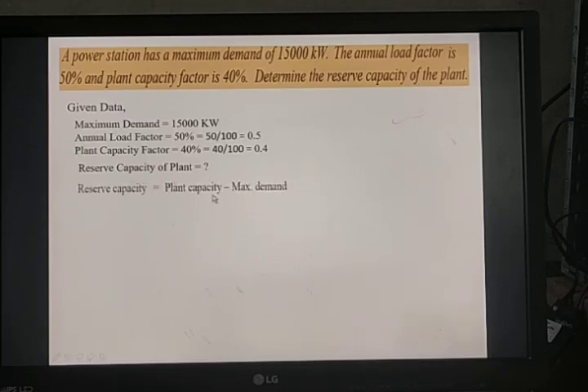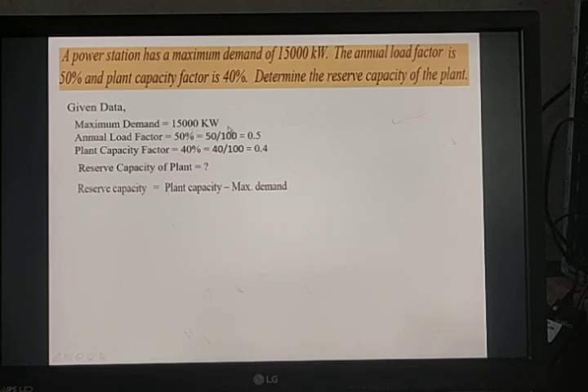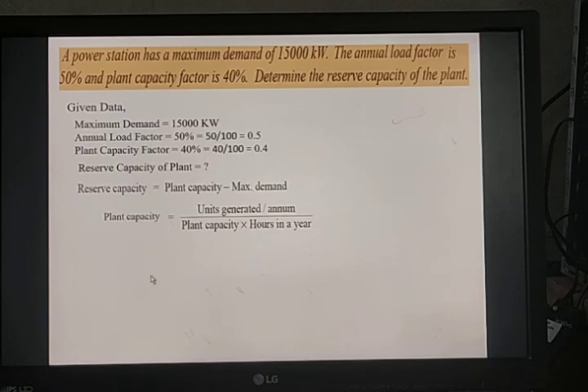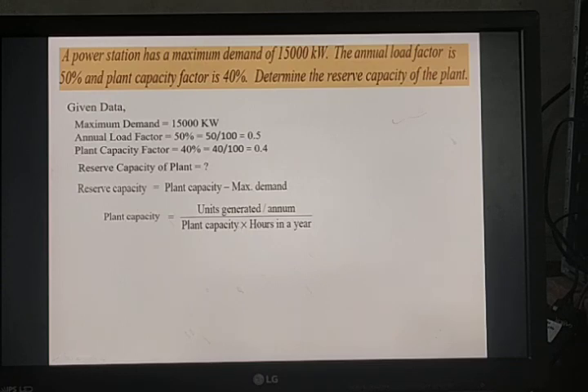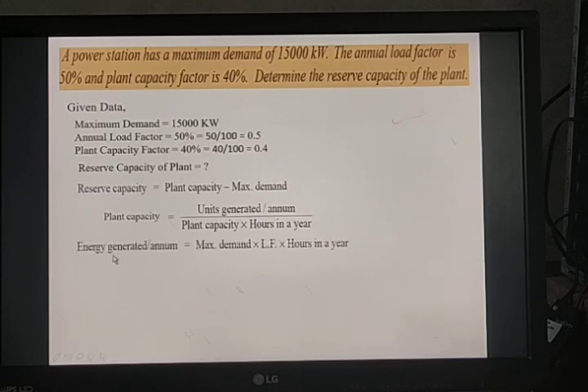Reserve capacity equals plant capacity minus maximum demand. The maximum demand is 15,000 kW, but plant capacity is not given directly. The plant capacity factor is defined as units generated per annum divided by (plant capacity × hours in a year). First, find units generated per annum: maximum demand × load factor × hours in a year.